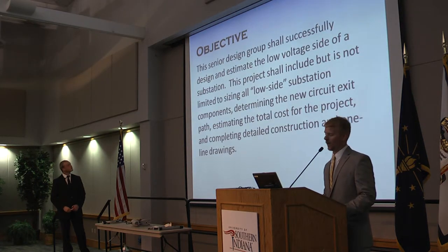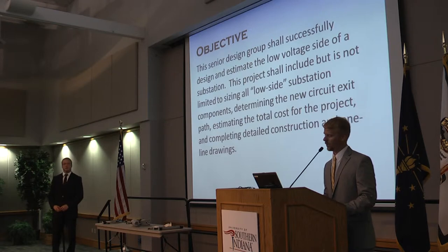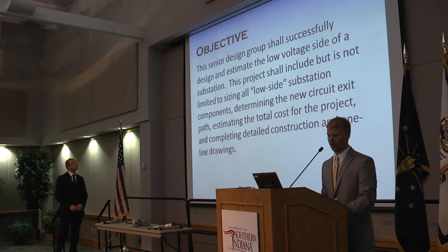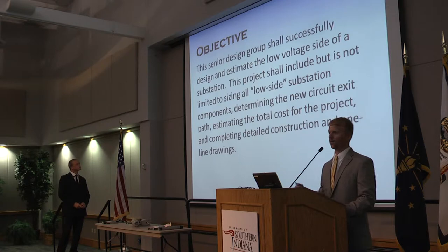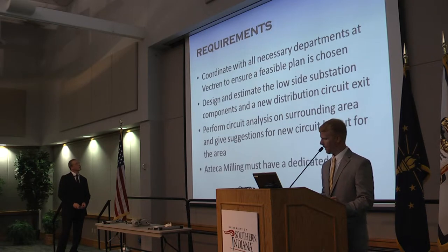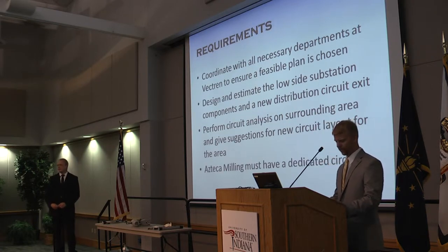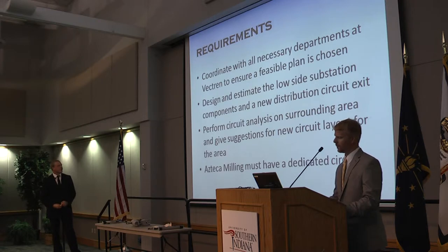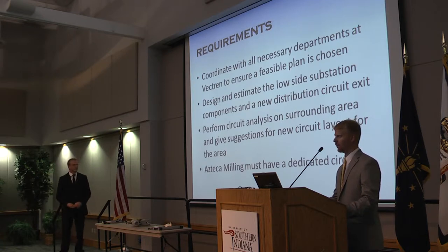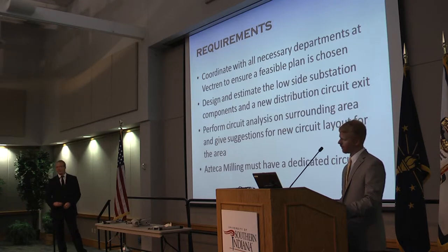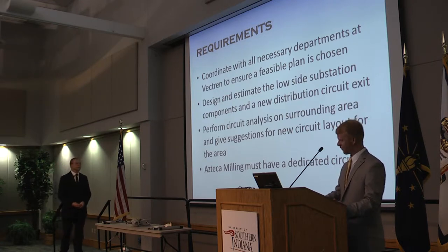So the objective that the lab group came up with is that we shall successfully design and estimate the low side voltage. We shall size all of the equipment necessary, excluding the transformer. We shall choose the circuit path. We shall estimate the total cost and complete detailed construction and one-line drawings. Requirements: we coordinated with all Vectren personnel necessary to complete this, design and estimate the low side of the substation, performed a circuit analysis on the surrounding area to give suggestions for new circuit layout, and as Azteca Milling must have a dedicated circuit because they are a key customer.